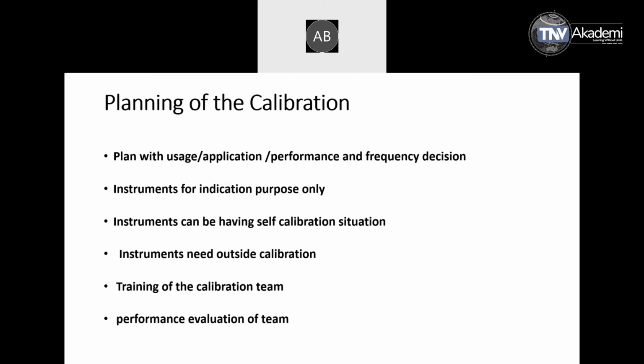Again, it is very important to have a trained calibration team, whether it is self-calibration, outside calibration, or in-house calibration. The calibration team should be trained adequately so that they are aware of the errors, the measurement traceabilities, and the measurement technology, and they know what kind of instruments to use and how. Because if they do a wrong measurement, the item will unnecessarily be accepted or rejected, when it should not have been. So training of the calibration team is important, as technology is changing, design is changing, and machines and instruments are being updated continuously. So their knowledge updation is very important.